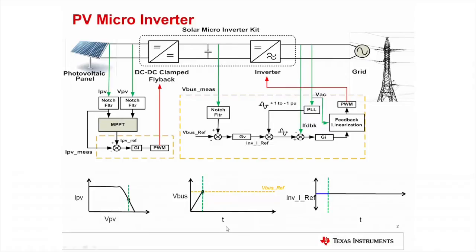Once this voltage reaches a DC reference point, the inverter operation starts. As the MPPT algorithm keeps moving the PV current towards the maximum power point, the DC bus can rise even further. To keep it constant, the inverter control loop will increase the current fed into the grid. Once the maximum power point is reached, the current stabilizes and reaches a steady state.